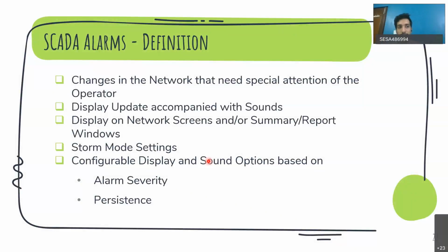Then another important feature with SCADA is the alarms. Alarms are actually any changes in the network that need special attention of the operator. Okay, so a particular breaker getting tripped because of a fault. That really needs the attention of the operator because he needs to attend to that fault immediately. So with the help of this alarm, he will immediately be notified that something wrong has happened in the network.